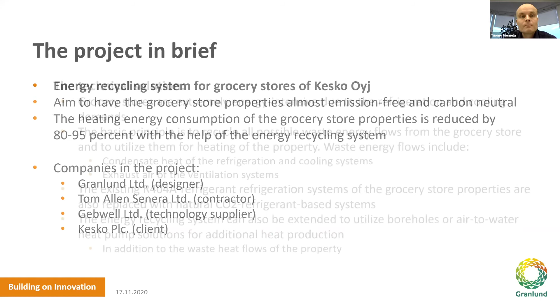Some brief technical background: these grocery stores are extremely energy intensive due to refrigeration and cooling demands. The basic principle of this concept is to recycle all possible heat flows from the grocery store into the heating of the building, and utilize them as efficiently as possible. The waste energy flows in these grocery stores include the major energy sources, such as the condensate heat coming from the refrigeration system and from the regular building cooling systems.